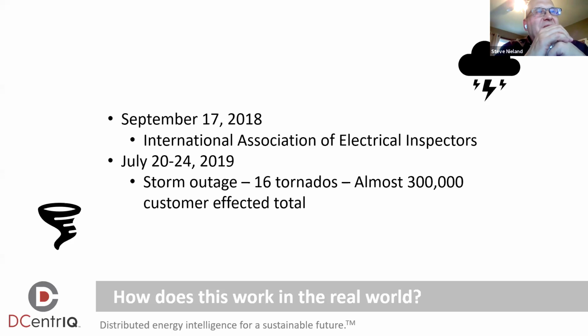They called the Nature Center, and the staff said, 'We've got power, we have a microgrid.' The Nature Center is normally open on Saturdays, and the staff working that day said the lights blinked once — they thought it was just a nearby lightning strike. What actually happened was the microgrid taking over as the reference source once the grid went down. They had no idea they were running off the microgrid from noon Saturday to midnight Wednesday, with no bumps and no problems.